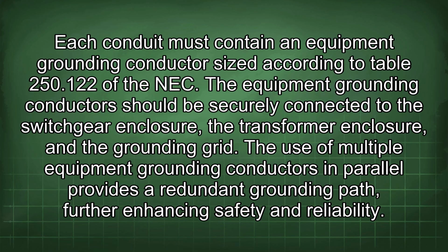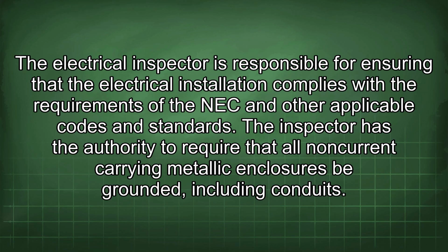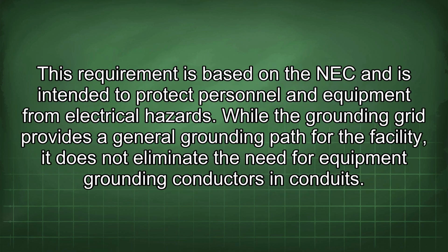The electrical inspector is responsible for ensuring that the electrical installation complies with the requirements of the NEC and other applicable codes and standards. The inspector has the authority to require that all non-current carrying metallic enclosures be grounded, including conduits. This requirement is based on the NEC and is intended to protect personnel and equipment from electrical hazards.